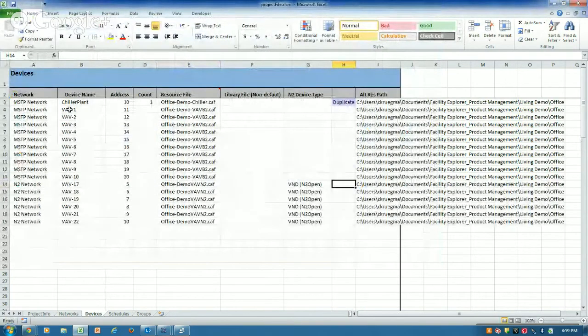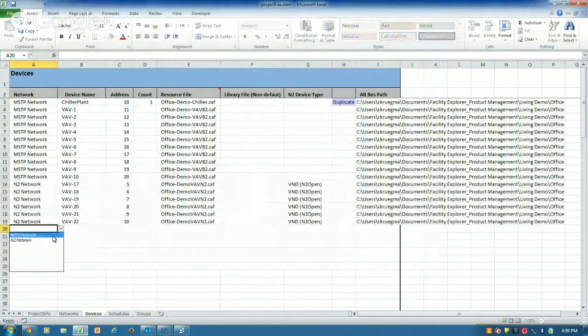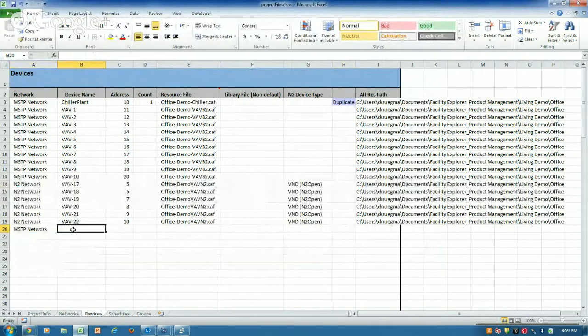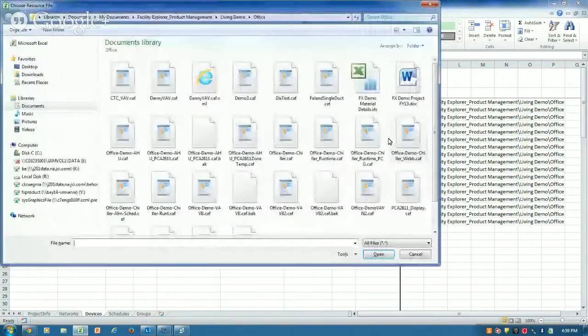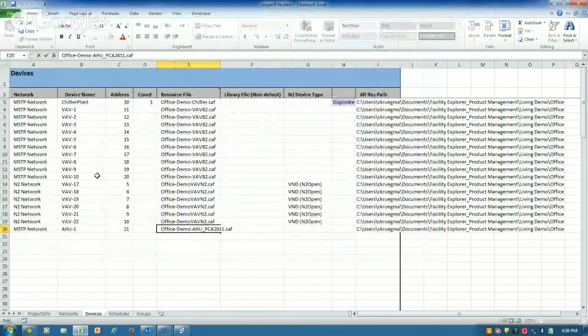So basically I've added a chiller plant and some VAV boxes. Let's go back to my BACnet network and add an AHU, at address number 21. I'll pick that CAF file. So now I've added all the devices that might be on my station, for instance.